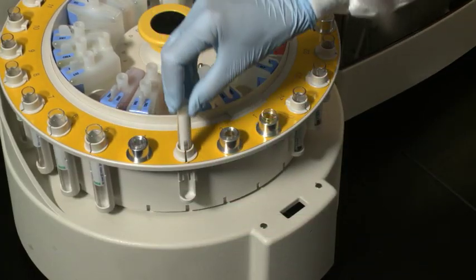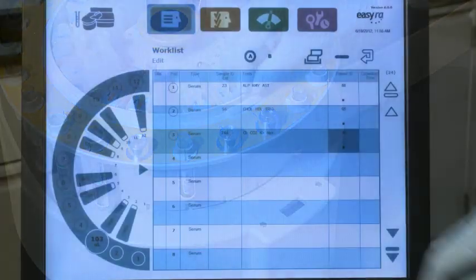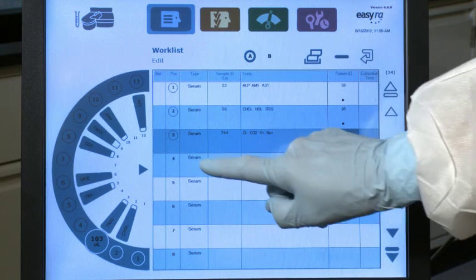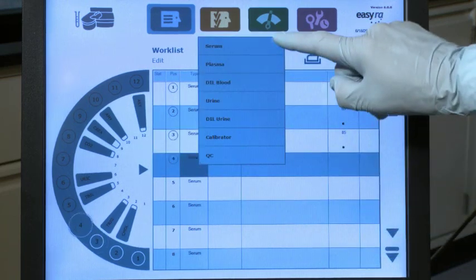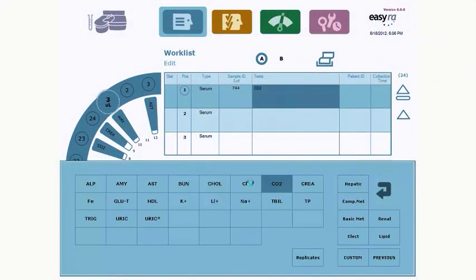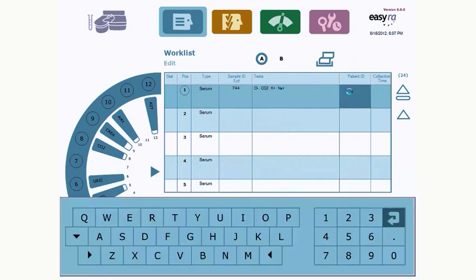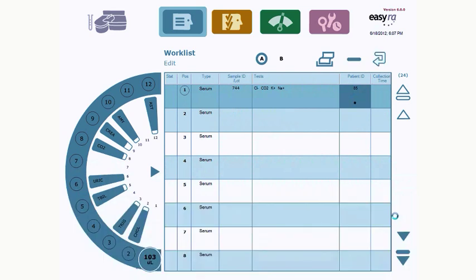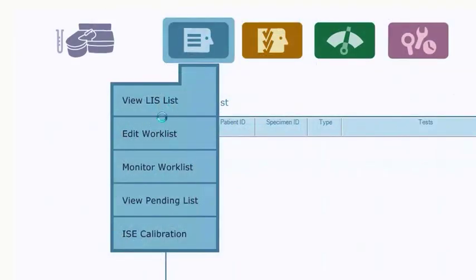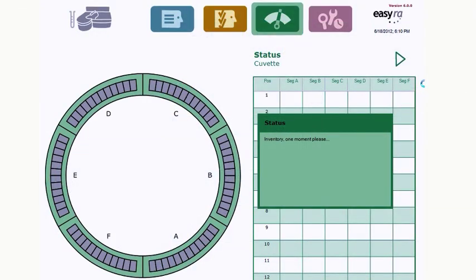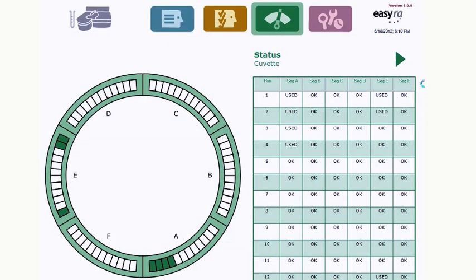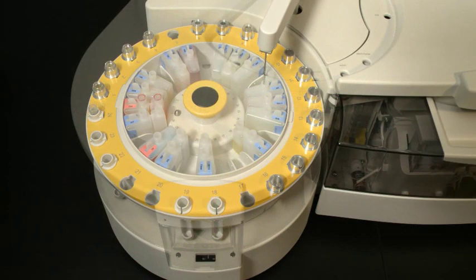Running samples begins with the work list. Enter samples or use the LIS interface to view samples and tests that were ordered. Choose tests individually or select from common panels. The work list menu provides a real-time display of sample status and automatic search of pending samples. You're in control—pause a run and edit as needed. The work list automatically performs an inventory of reagents and cuvettes prior to every run.